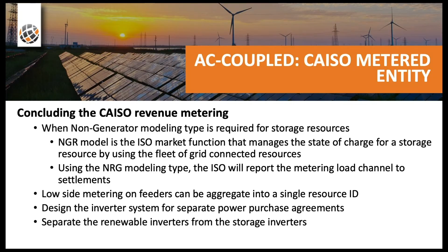Or separating how you're going to market this unit on the ISO market systems. So in order to manage that aspect, the inverters are the separation for each PPA. In other words, an inverter can't be split in half with ISO metering, one to one resource ID and one to the other. Usually each PPA is a representation of one resource ID.